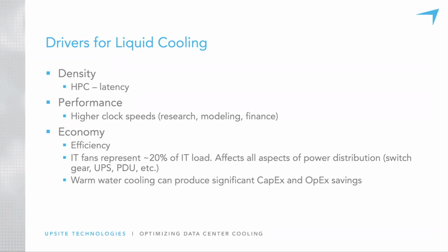So that is a significant load that can go away or largely go away with the adoption of liquid cooling. There are other aspects of liquid cooling that drive efficiency, such as using warmer chilled water, which can improve the efficiency of the chiller or provide other options for using waste heat from other processes, such as in warm water cooling. That can substantially reduce the CapEx and OpEx of the facility. A whole presentation could be devoted just to each of the bullets on this slide, but we're going to touch on the high-level issues in this presentation.